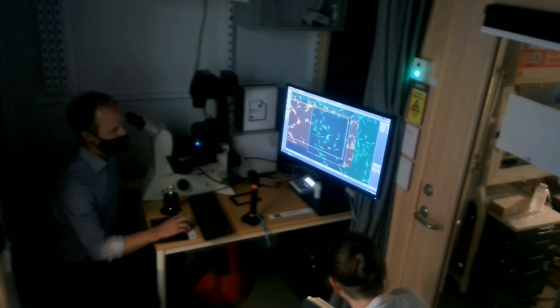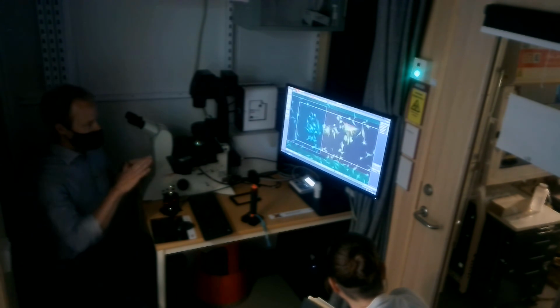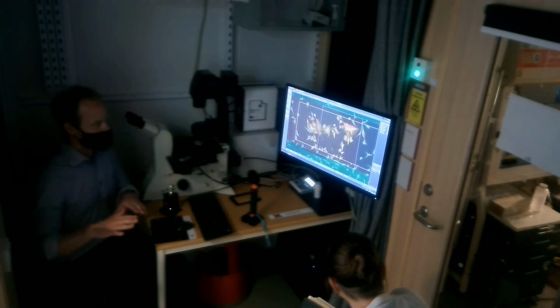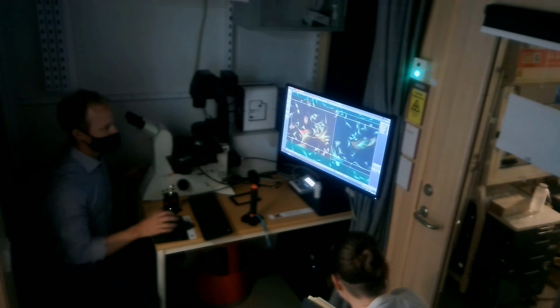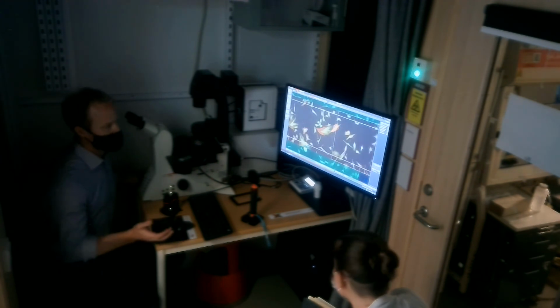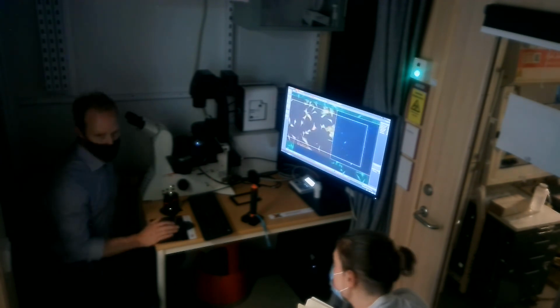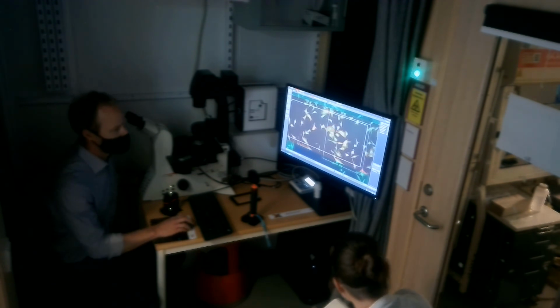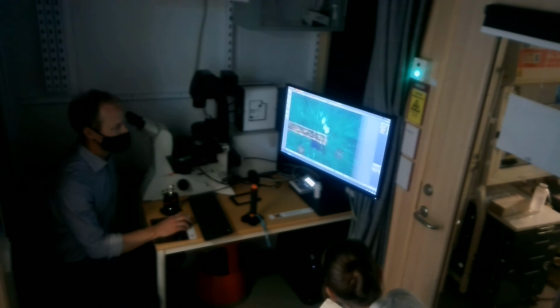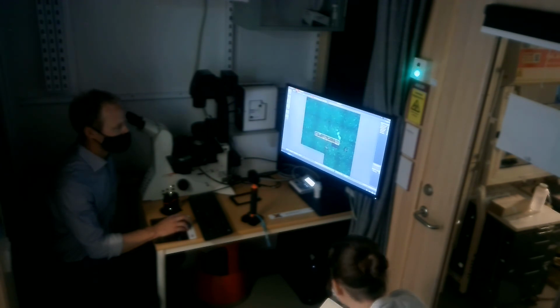So what will happen now when I run this experiment is that it will adjust the Z as it moves through this. It will interpolate between these two points. So as long as my sample is flat, then everything should be in focus. In some cases my sample might not be flat, but this is the way to then get the focus over this whole range. So that would be the same if you have a larger tile scan. You might need to...